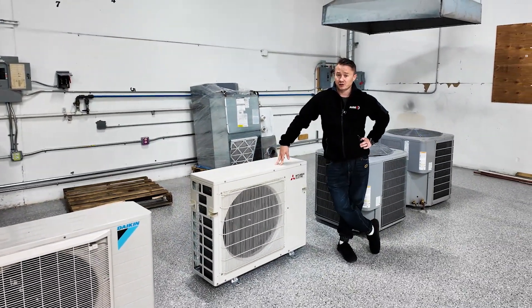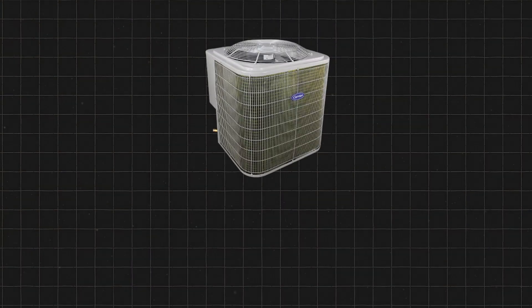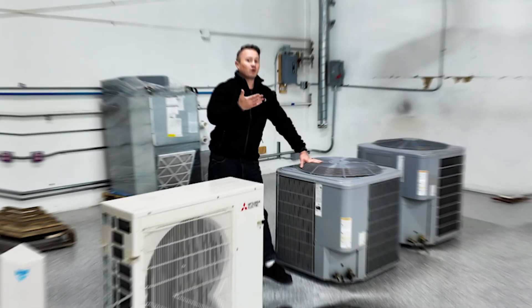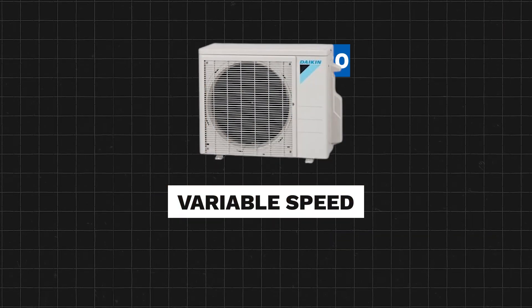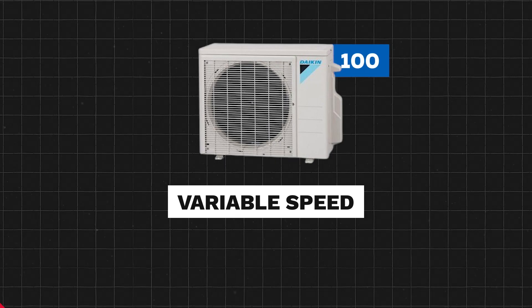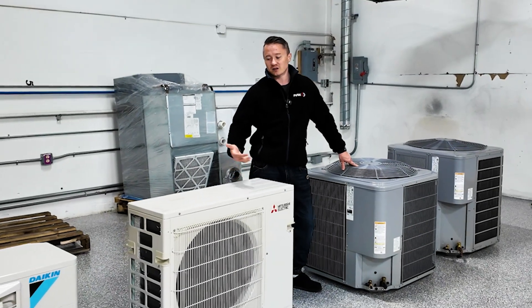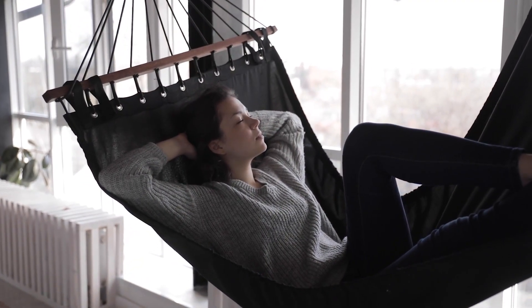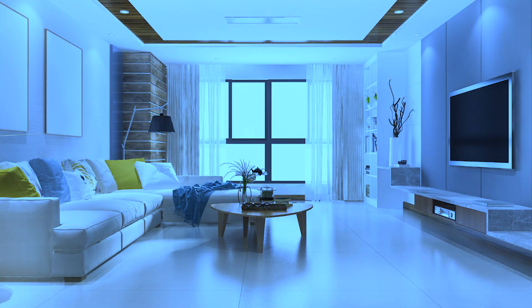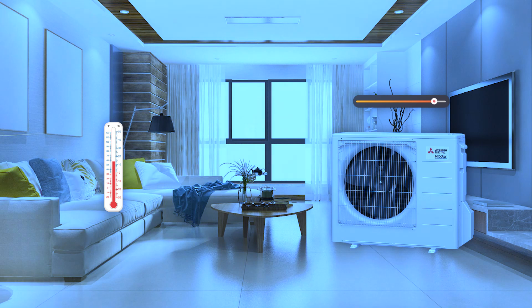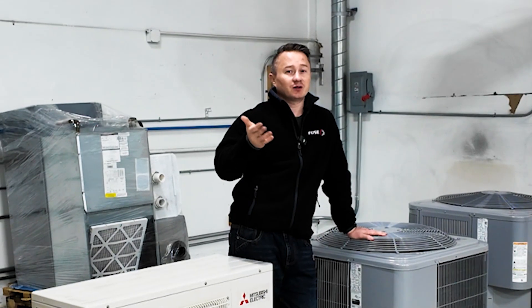Why do I compare with two slim units like this? Because these units have even more functions. A conventional unit runs at only one speed — 100% capacity, constantly. But this slim unit can run at 5, 10, 15, 20, 30, 60, 90, or 100 percent depending on the situation. It will start at 100% when your house is very cold, then decrease capacity as it approaches the target temperature, and eventually just maintain the needed temperature.